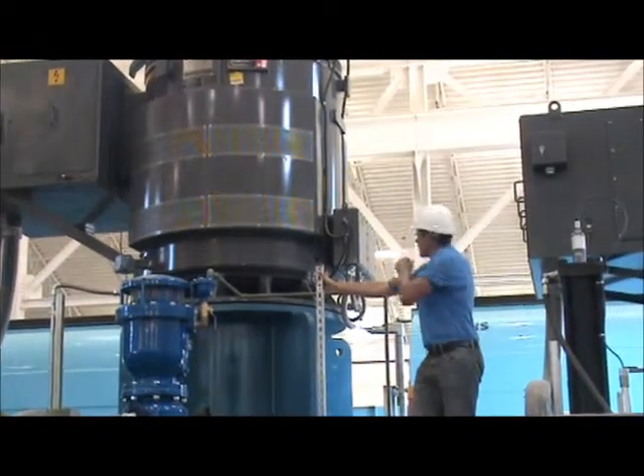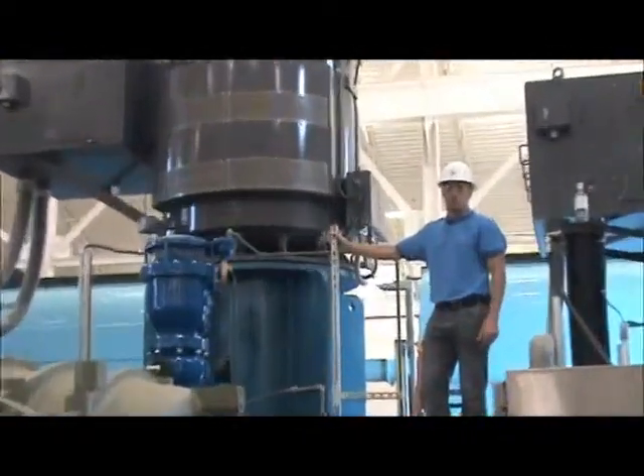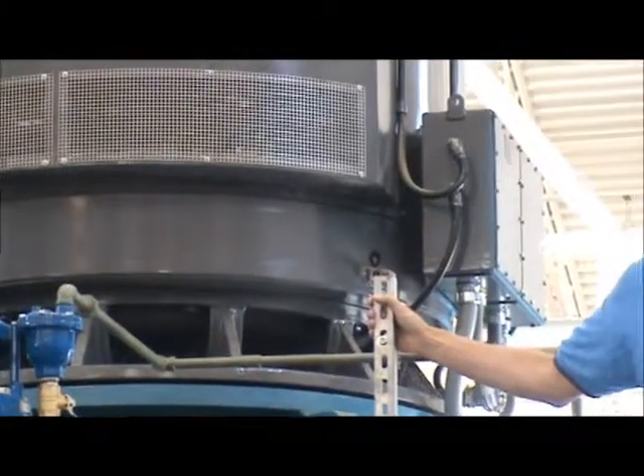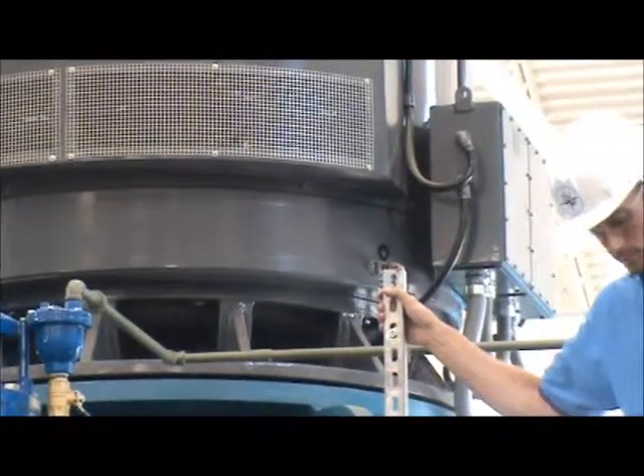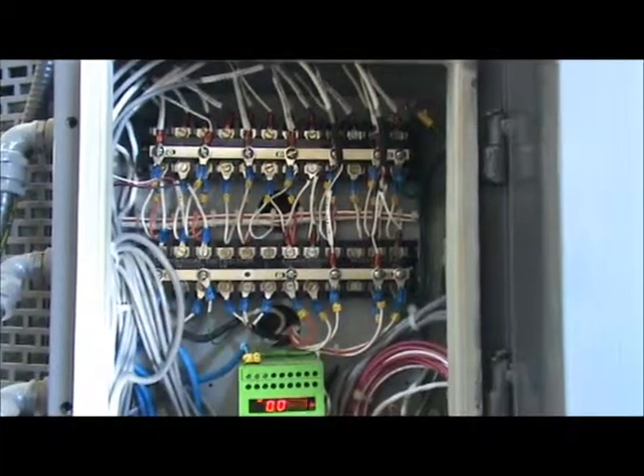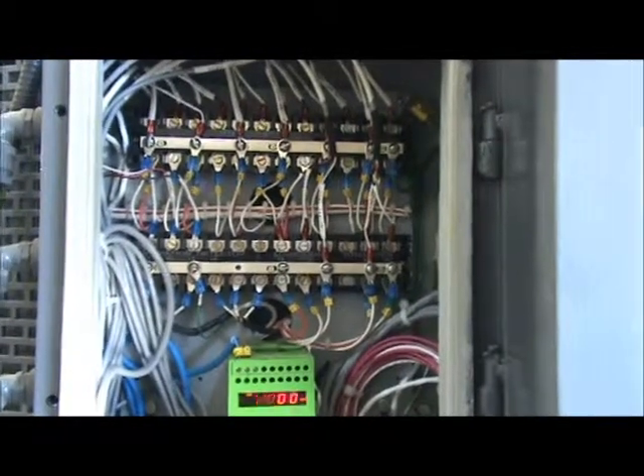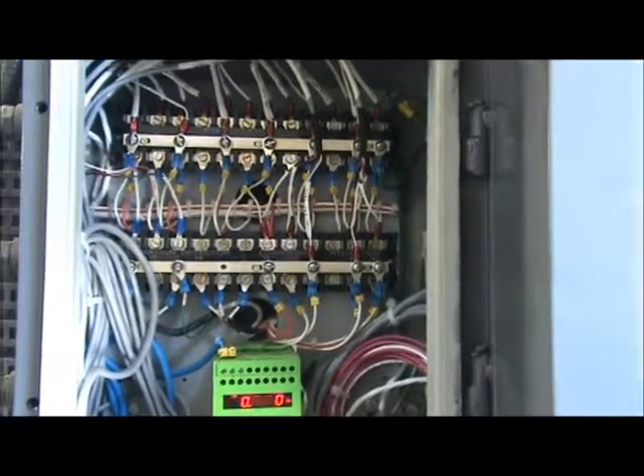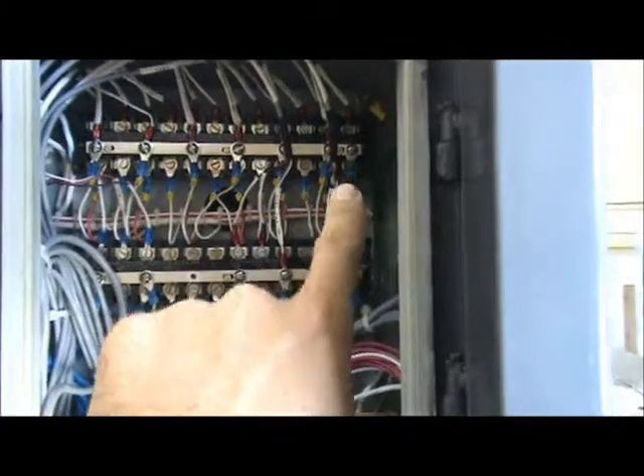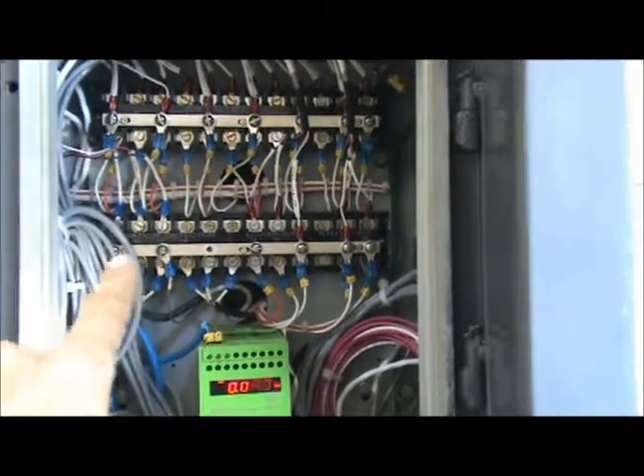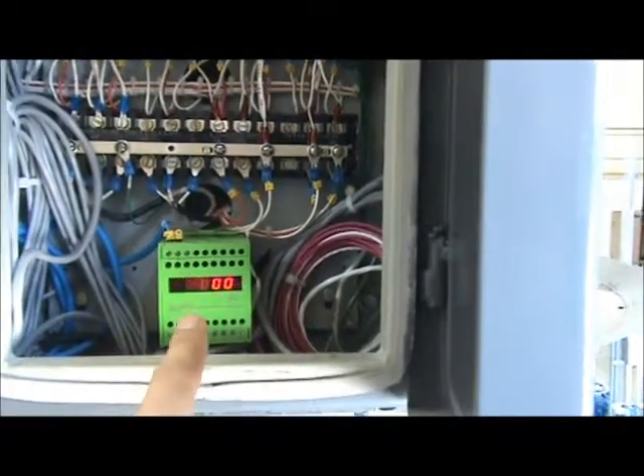And then over here on the right side, we have a smaller terminal box, which I'll show you inside in a second. Inside the small terminal box, we have our RTD connections, our vibration sensor, as well as a 0-speed sensor.